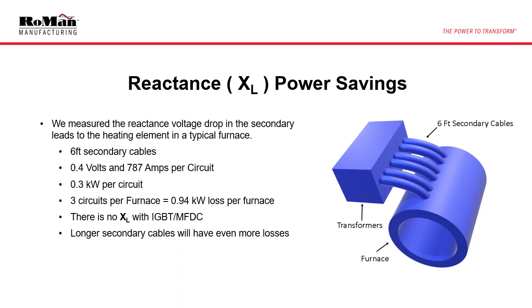Each heating element was conducting 787 amps, giving us a total of 0.3 kilowatts per circuit. With 3 circuits per furnace, we have a total loss of 0.94 kilowatts in each furnace. These losses add up over time, and with longer secondary cables, you can expect to see even more dramatic losses. With our IGBT MFDC technology, this loss is completely avoidable.